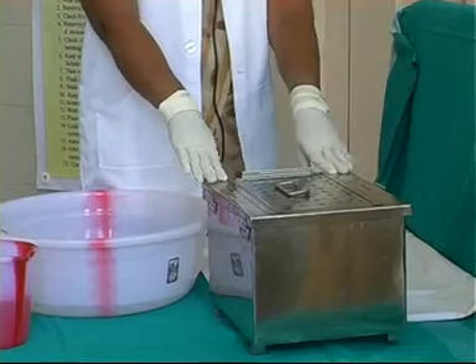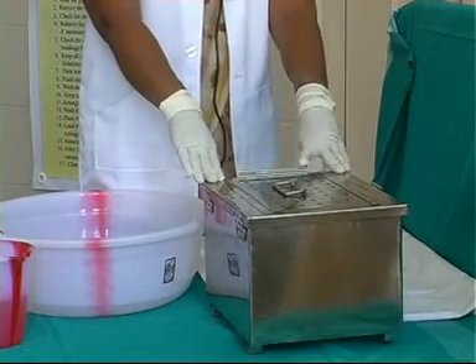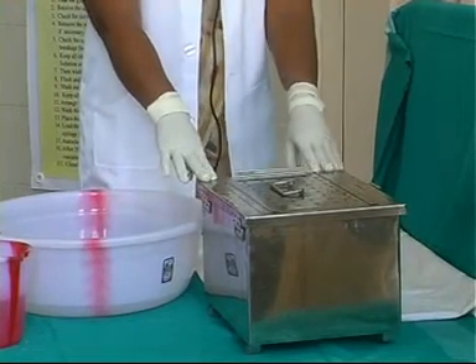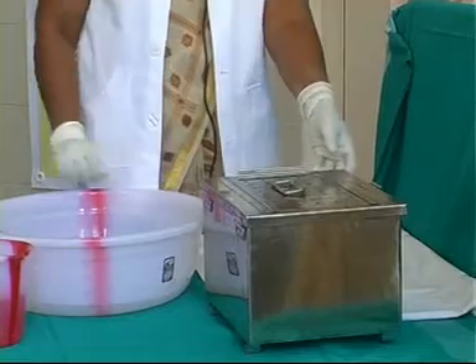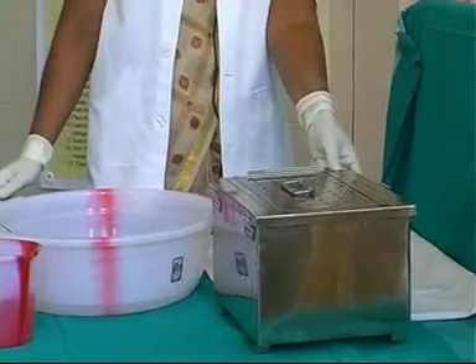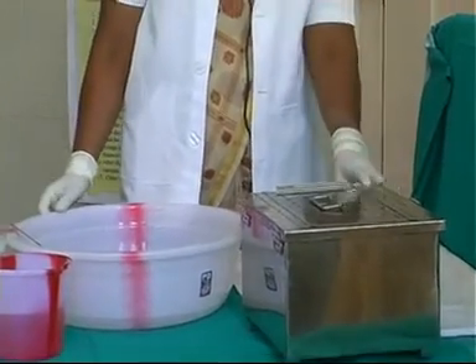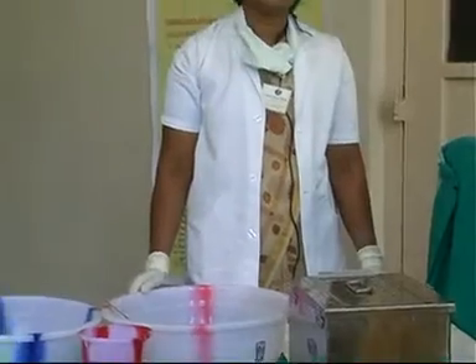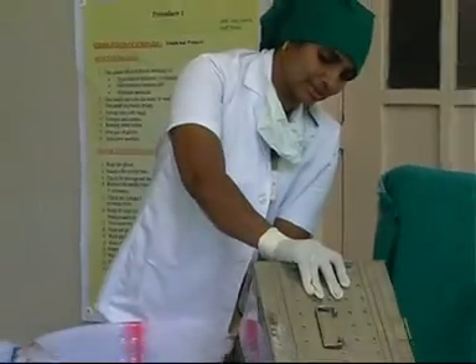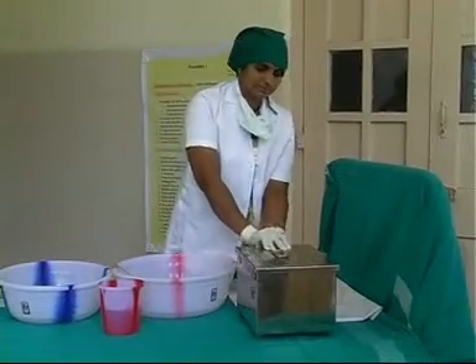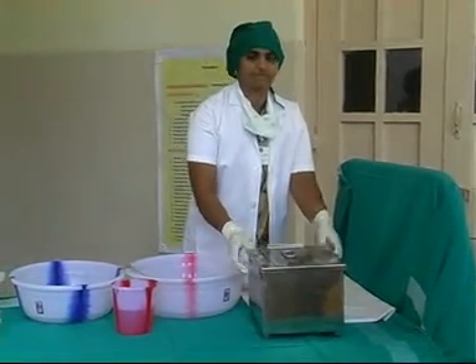The syringe bin has to be kept in the autoclave machine at 120 degrees centigrade, 20 lb pressure for 30 minutes. After 30 minutes, the machine has to be turned to fast exhaust mode for 15 minutes. After that, again it has to be kept for 15 minutes vacuum dry. When the autoclave machine becomes cool, take out the syringe bin, close the holes which we opened before keeping inside, and keep it into the sterile area.